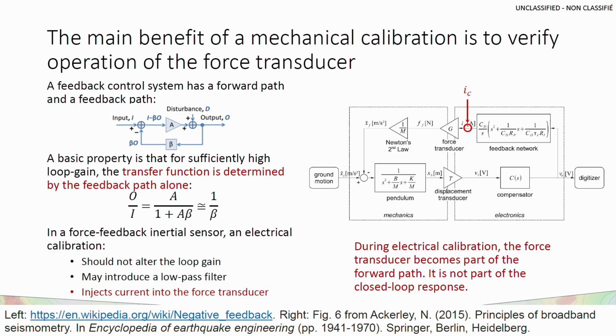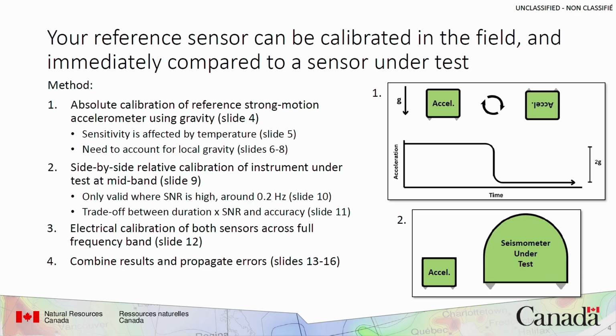So, knowing this, I'm proposing to only try to do absolute calibration at mid-band in the field, and really focus on this one otherwise unmeasurable-by-electrical-calibration parameter, the force feedback transducer.